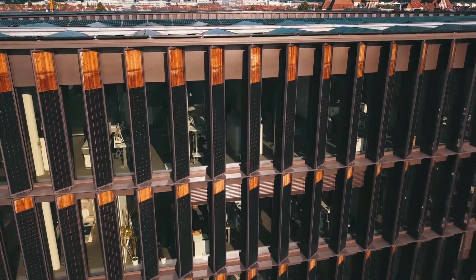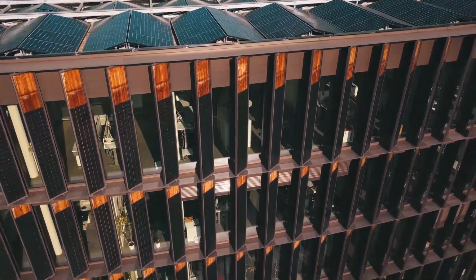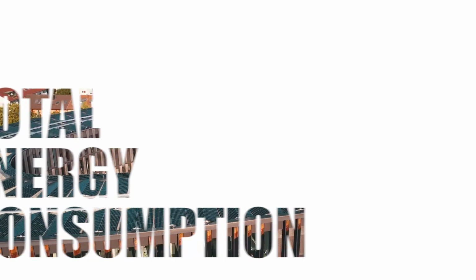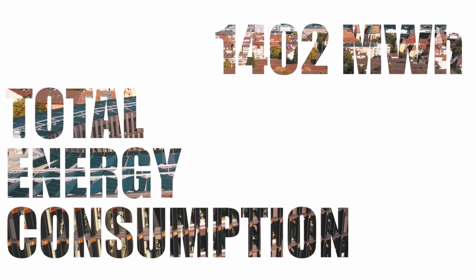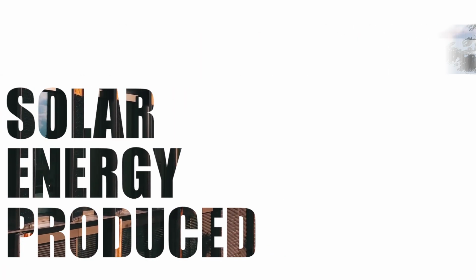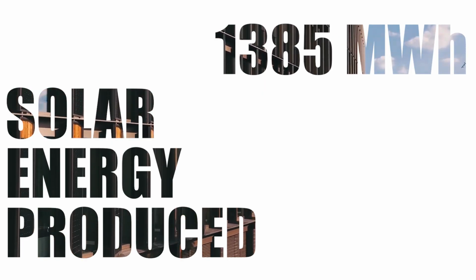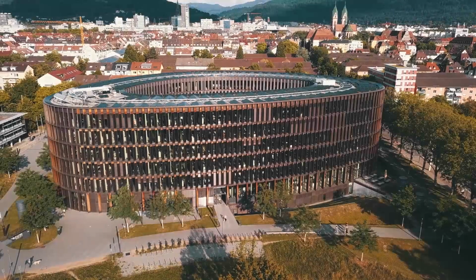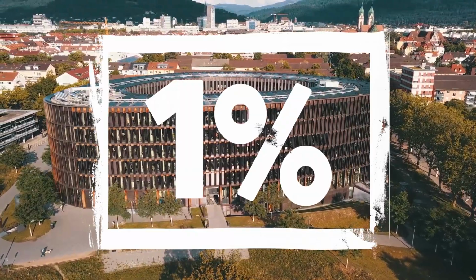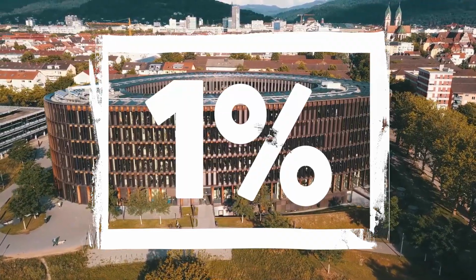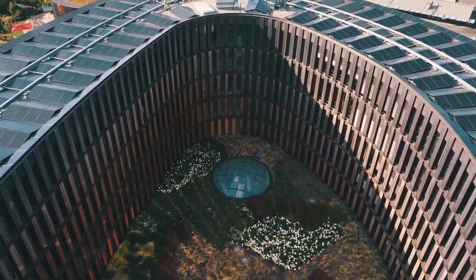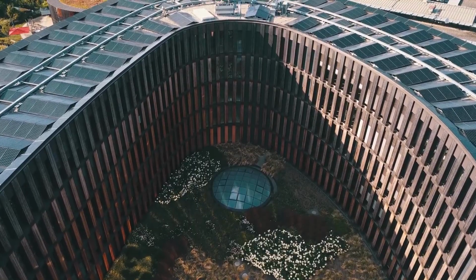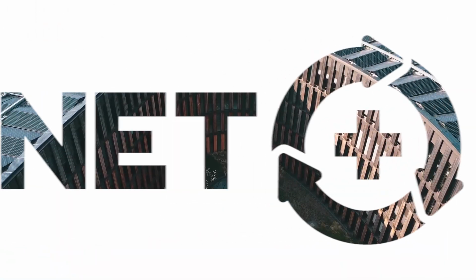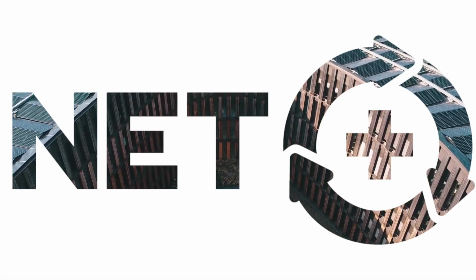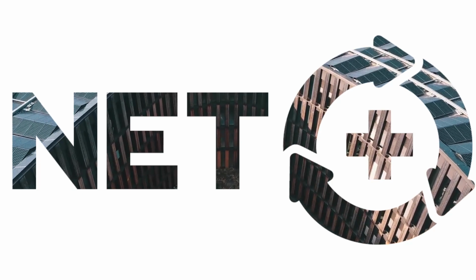At the end of a full year, the numbers speak for themselves. Total energy consumption, 1,402 megawatt hours. Solar energy produced, 1,385 megawatt hours. That's a difference of just 1%, effectively net zero. If the backup boiler were powered by biogas instead of natural gas, the town hall would actually be net positive, producing more energy than it consumes.